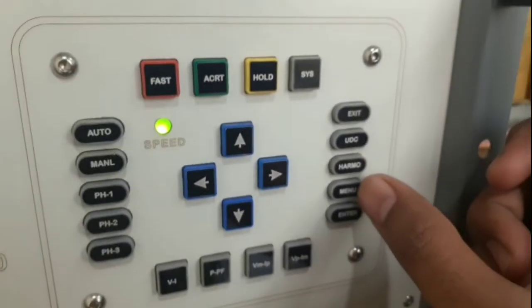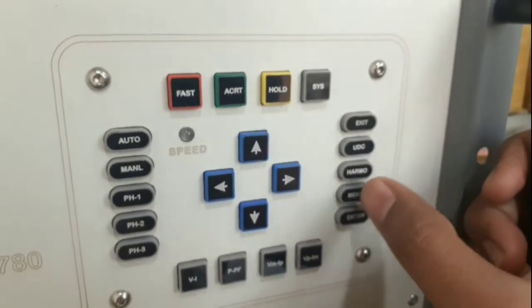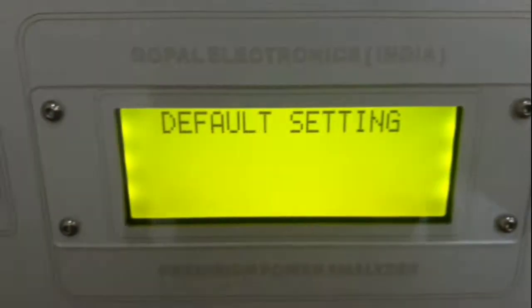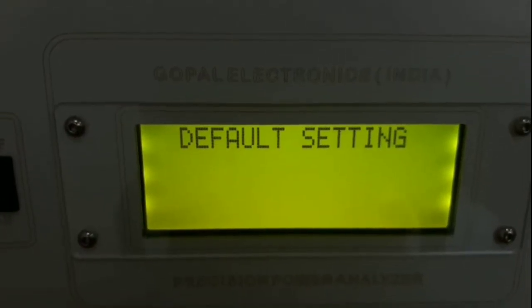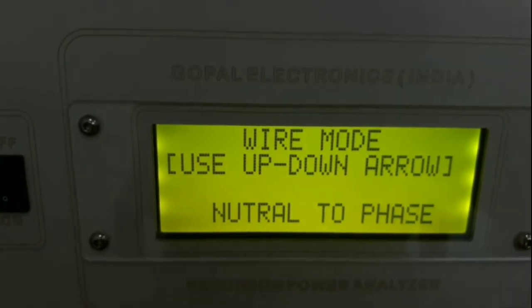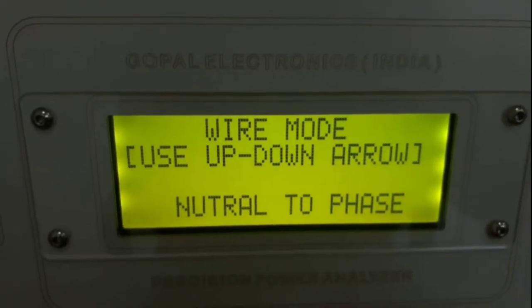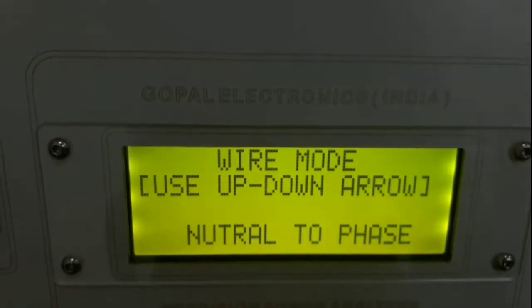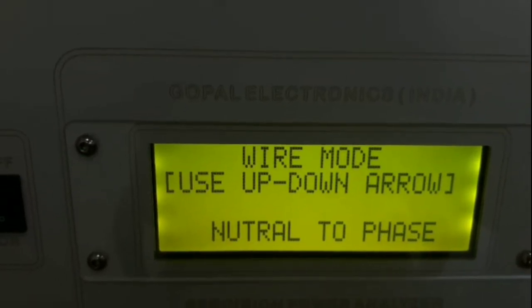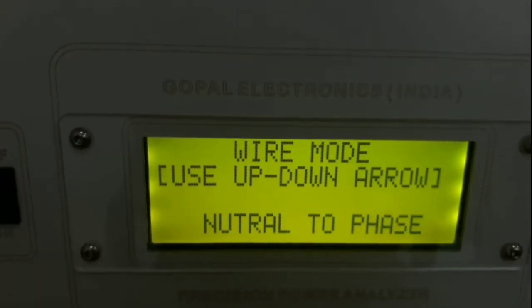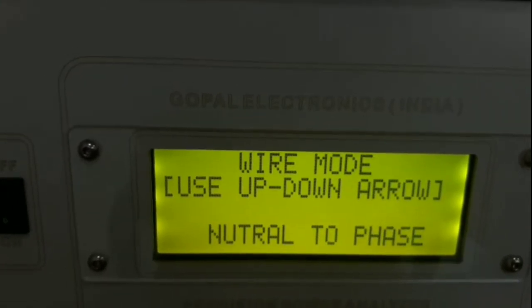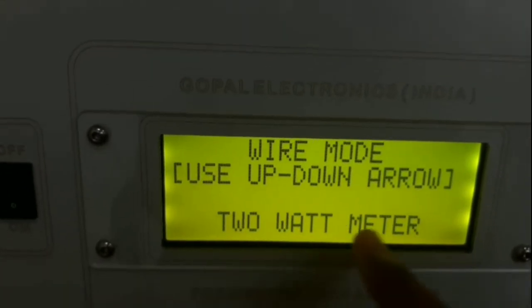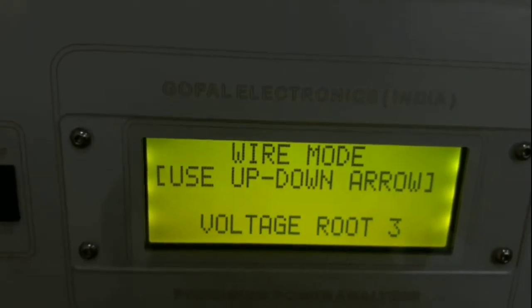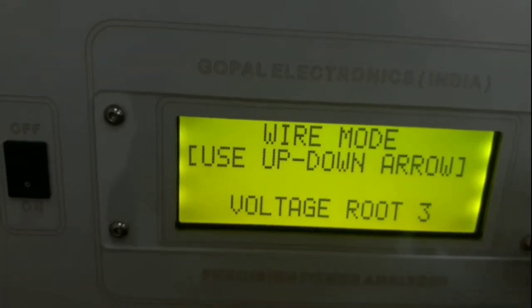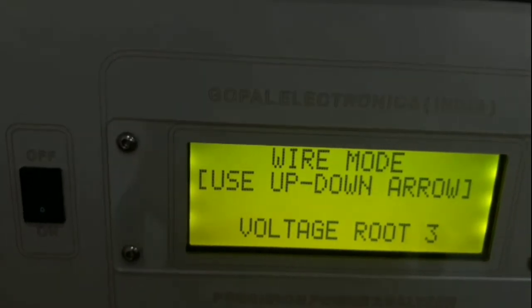Here the menu key is also given. By pressing the menu key you can do settings. Press the menu key again, and you will enter wire mode. Here it is written use up down arrow to change wire mode. Press the up key. We are in neutral to phase mode. Press the up key. This is 2 watt meter mode. Press the up key. This is voltage root 3 mode. These 3 wire modes are given. Select your wire mode and press enter.